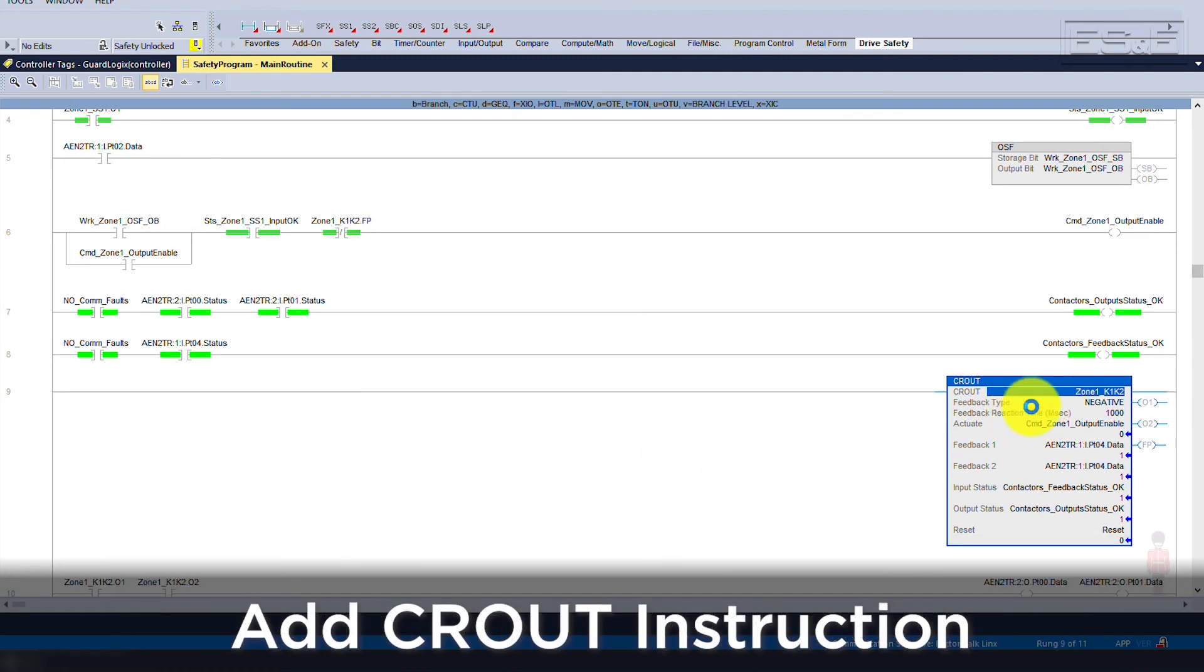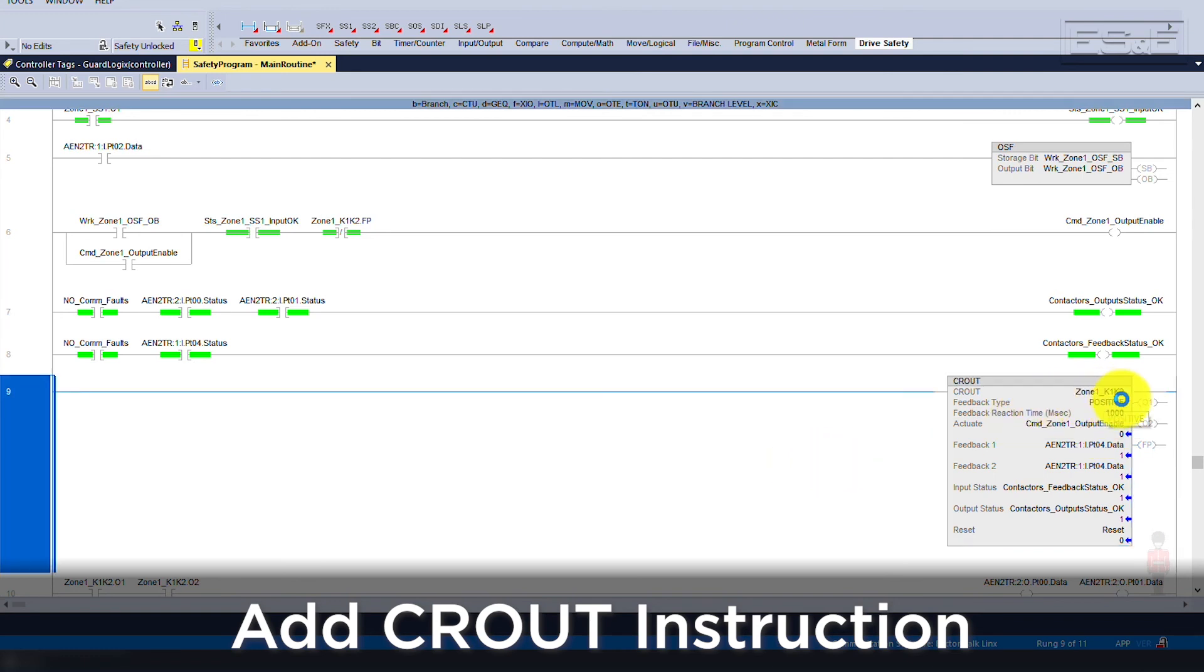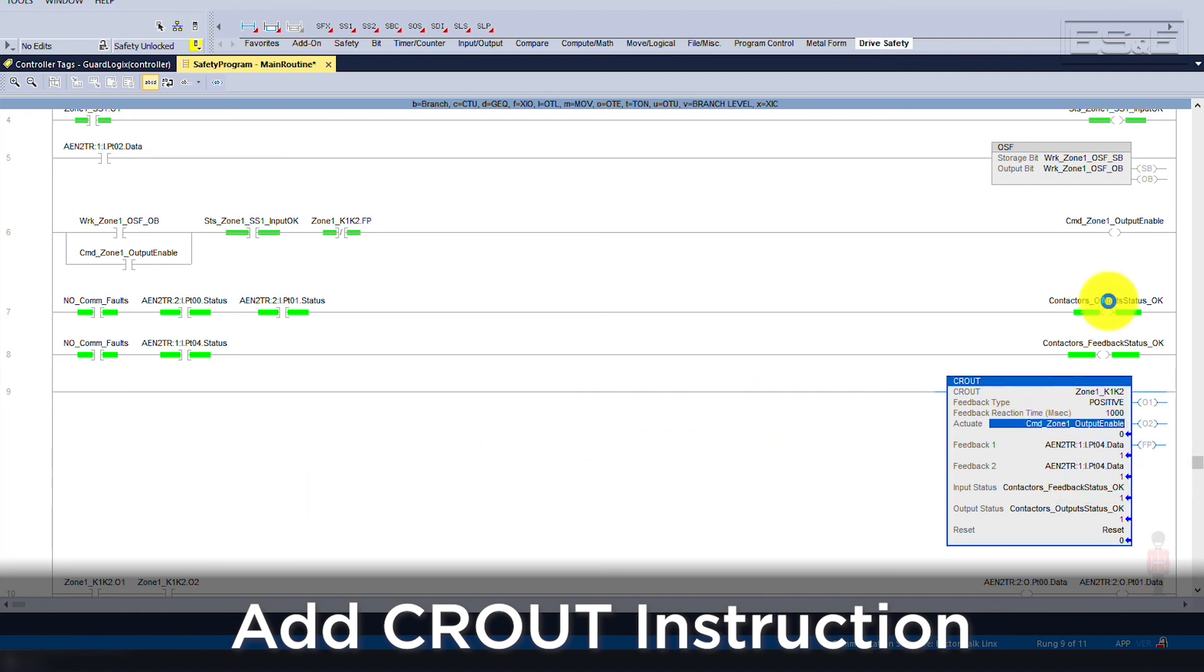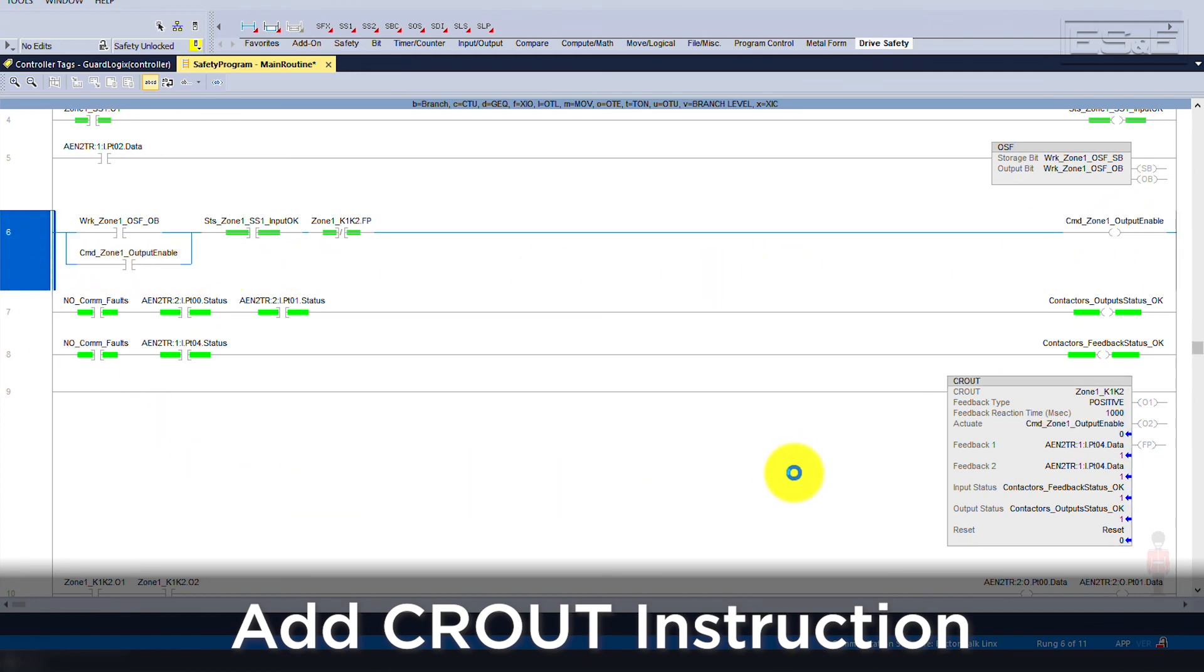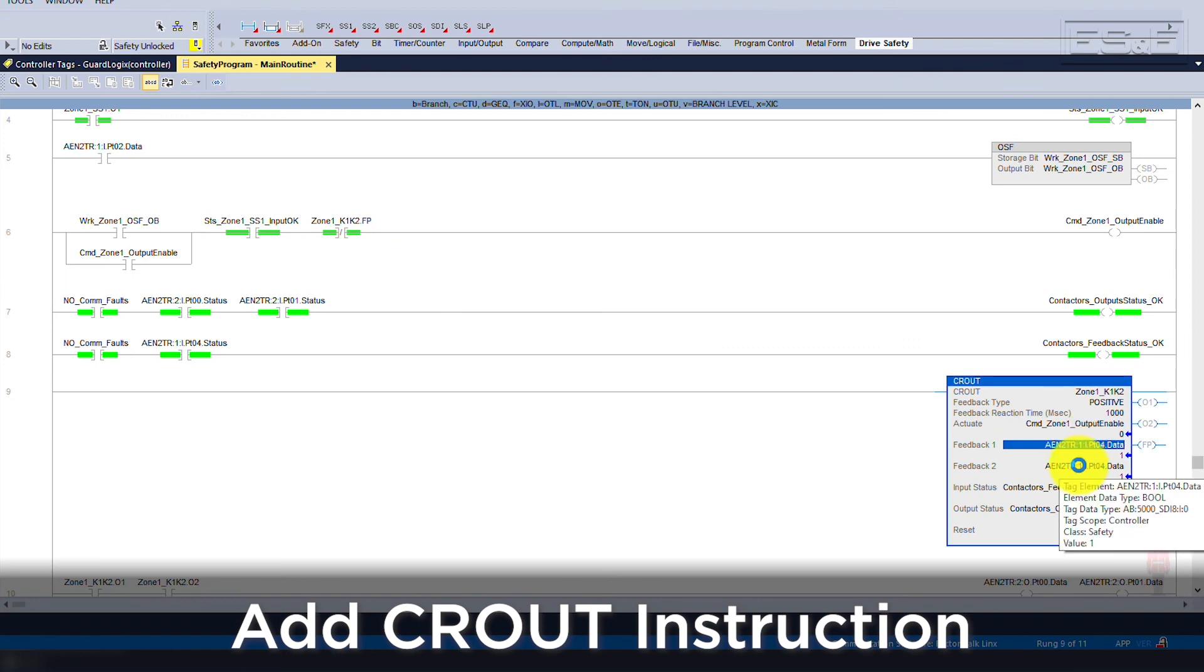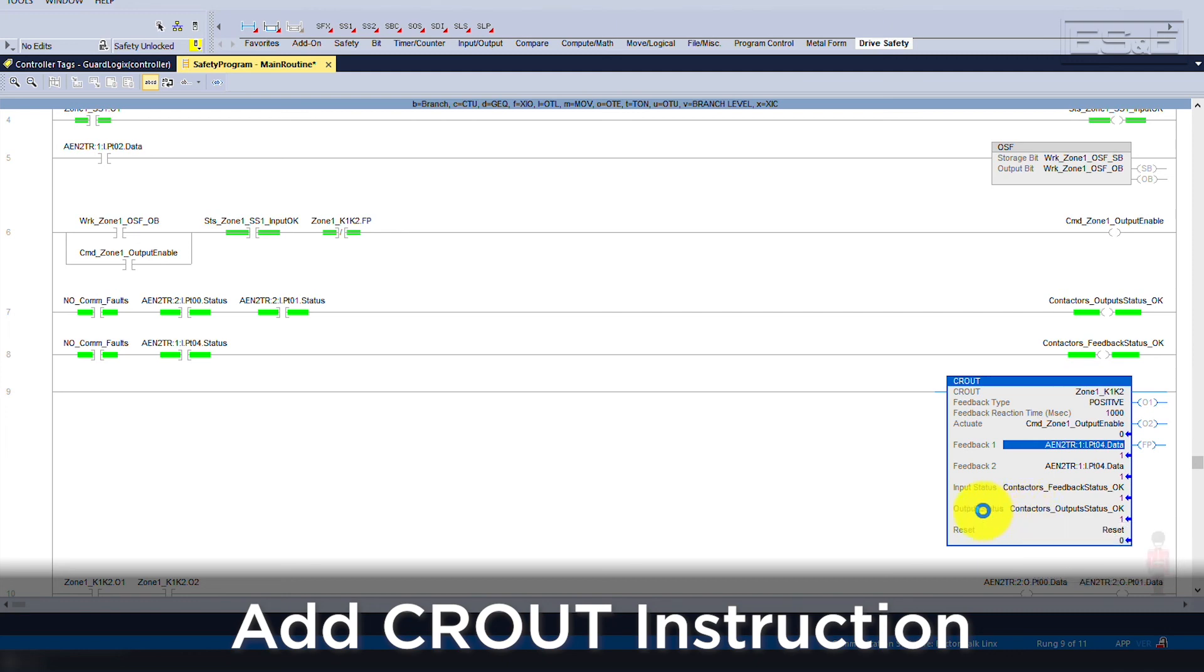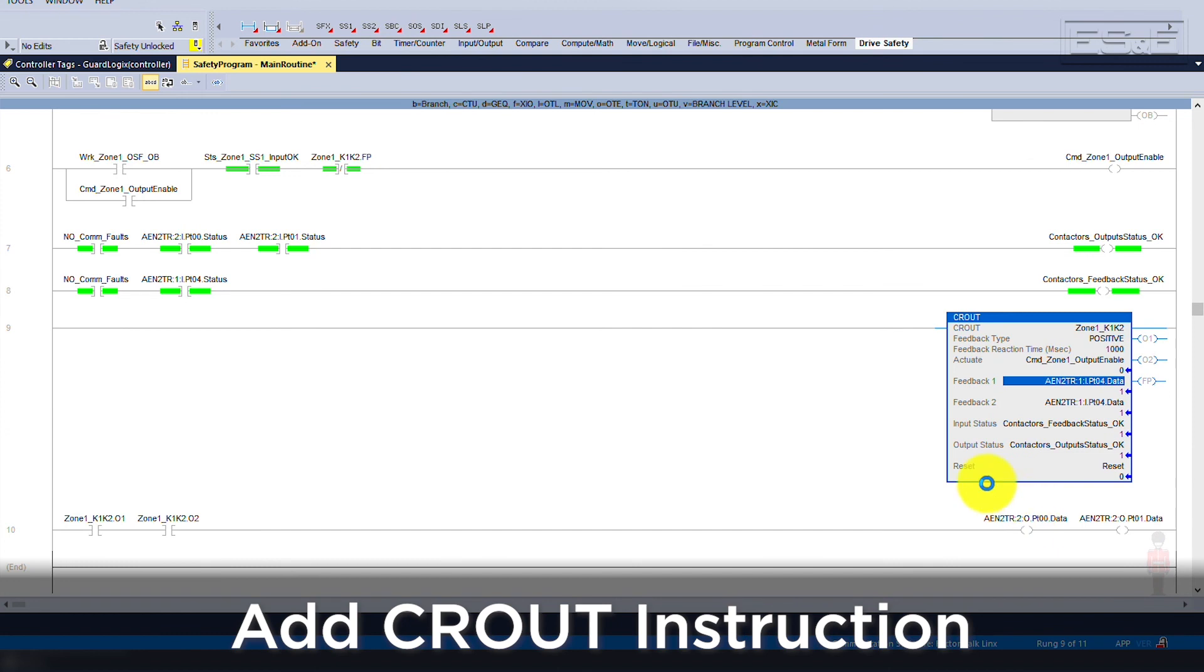Now we will create a CROUT instruction with a feedback type of positive, which means the feedback signal will follow the output state. If the type is set to negative, that means the feedback is the opposite of the output state. Next is the feedback reaction time, which dictates how long the instruction will wait after the outputs are energized before the feedback signal is verified. Followed by the Actuate tag, which is the logic we created to enable the outputs. Then the feedback signals. You can configure the instruction to utilize two separate feedback signals, but that is not necessary, so you can use the same tag for both fields. That is then followed by the status tags created based on both the feedback status for our input status as well as the output status for the actual output module.